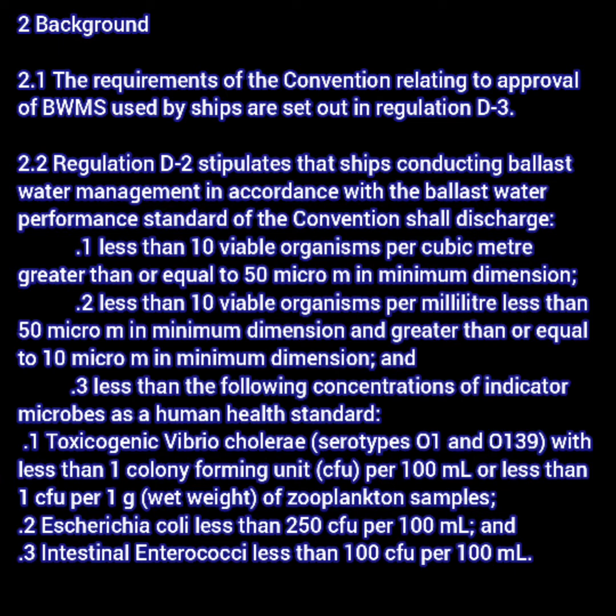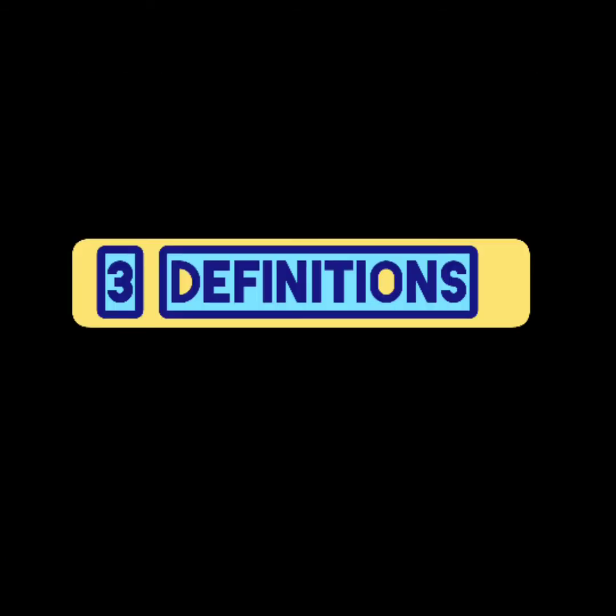As per the D3 standard, D3 is about the approval requirement for a ballast water management system. It also talks about regulation D2, which is about ballast water performance standard — basically the amount of organisms which must be present after treatment. In the background, D2 standards are repeated, such as 10 viable organisms per cubic meter greater than or equal to 50 micrometers in minimum dimension.